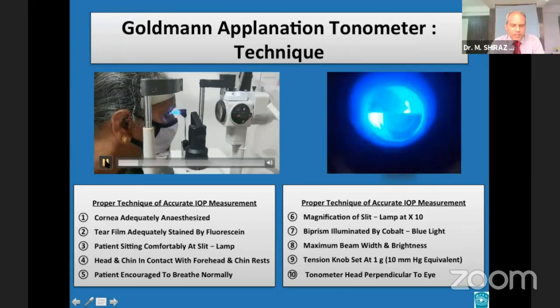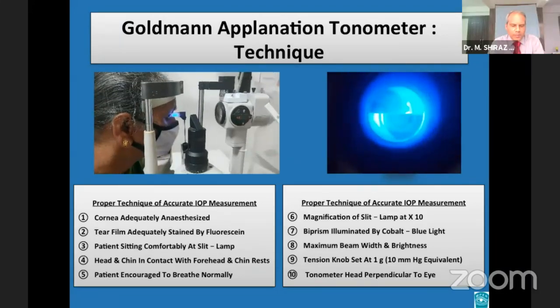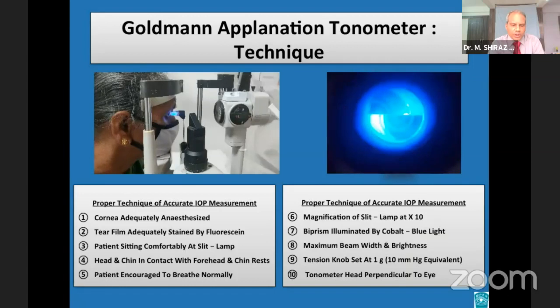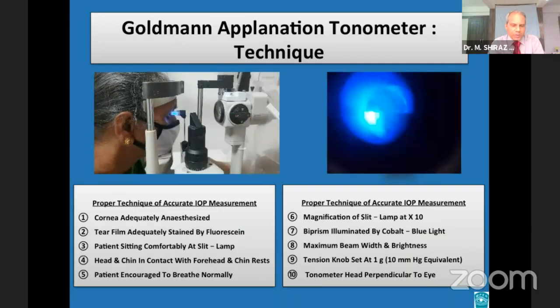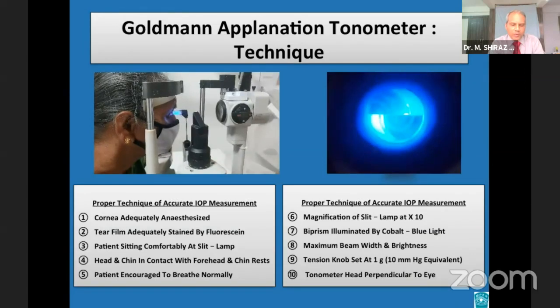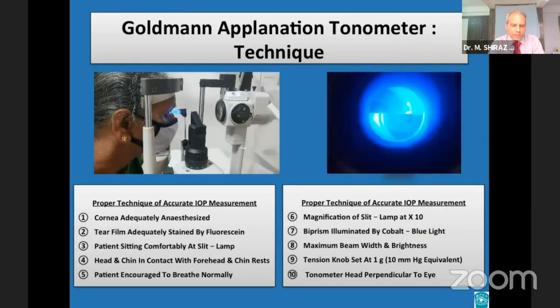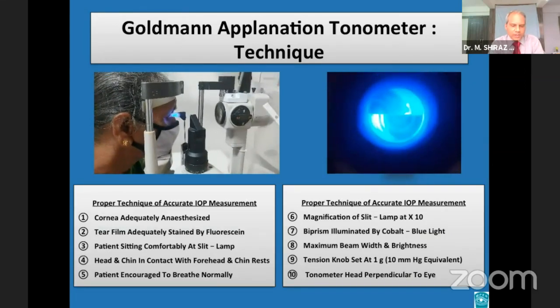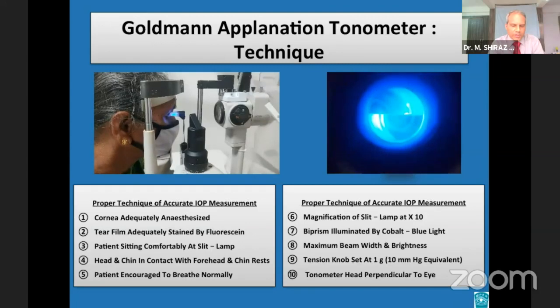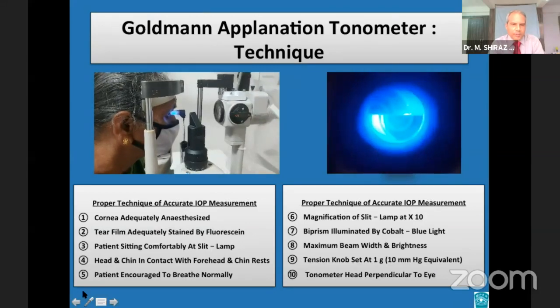When the tip of the biprism approximates the cornea, the biprism splits the circle of contact into two semicircles. If the two semicircles are properly aligned, they undergo a rhythmic movement in response to the cardiac cycle. The tension knob is rotated until the inner borders of the fluorescing rings touch each other at the midpoint of their pulsations.